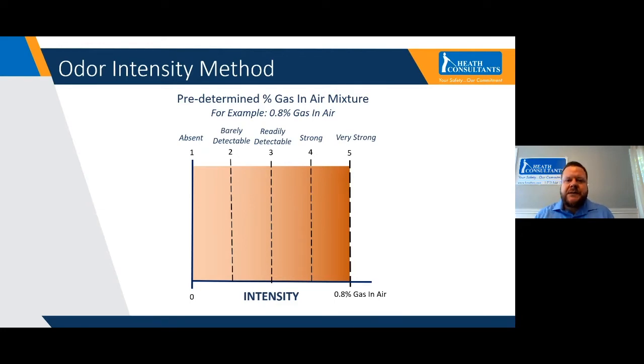So the odor intensity method is where you introduce gas into the instrument at a known quantity, or a predetermined gas in air mixture. So for this example, if your operator states, we want to do the odor intensity method at 0.8% gas in air, you would crank up the device, introduce 0.8% gas in air, and then you'd have the operator or technician smell the instrument. And at that point, they would decide, is that smell very strong? Is it readily detectable, or is it hardly detectable or absent? And they would rate that smell on a 1 to 5 scale. And this is another way to determine whether you have adequate odorization throughout your system, by tracking the intensity of the natural gas throughout.